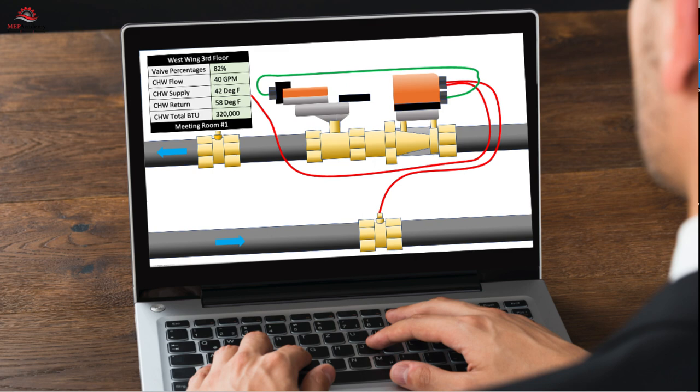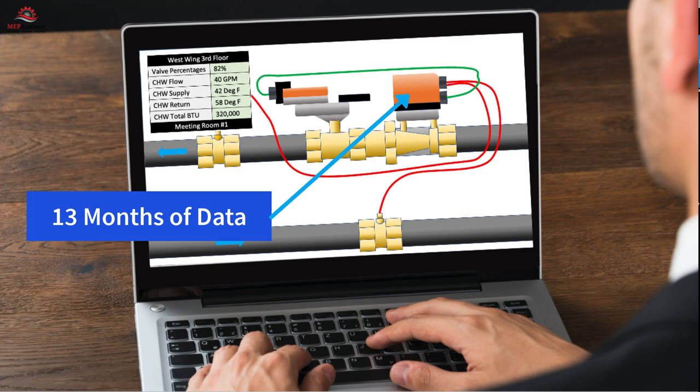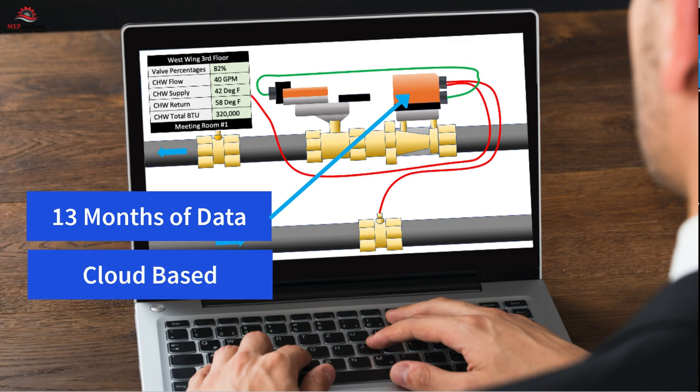Building management system integration. The energy valve has the capability to connect using Modbus and BACnet protocols, in addition to the capability to connect securely to the internet. This allows for monitoring of temperatures and flows, which can be used to bill tenants for energy consumption. The energy valve logs the energy consumption for up to 13 months on the valve, or for indefinitely when connected to the cloud.